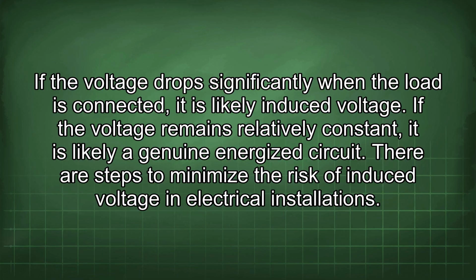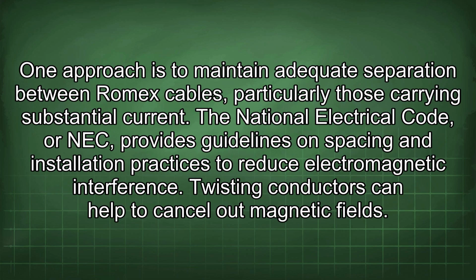There are steps to minimize the risk of induced voltage in electrical installations. One approach is to maintain adequate separation between Romex cables, particularly those carrying substantial current. The National Electrical Code, or NEC, provides guidelines on spacing and installation practices to reduce electromagnetic interference.